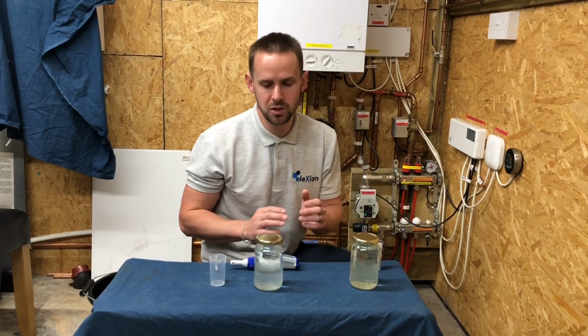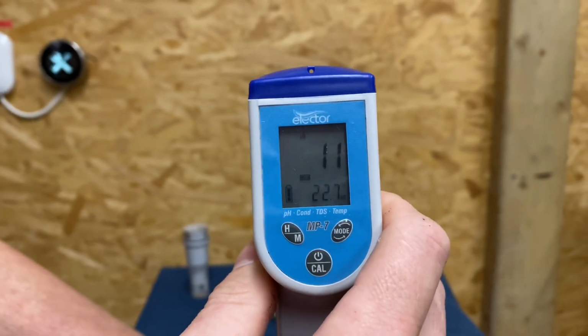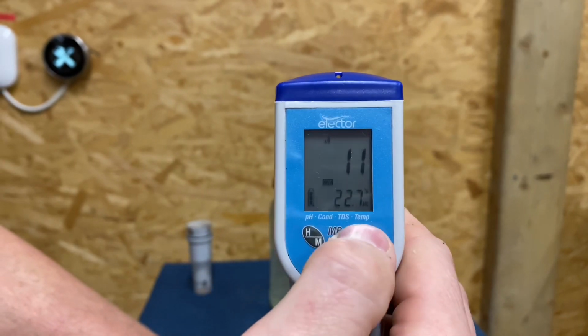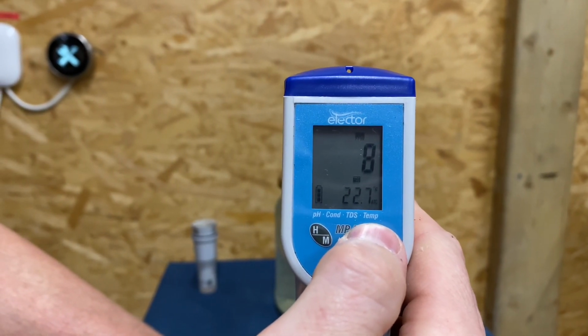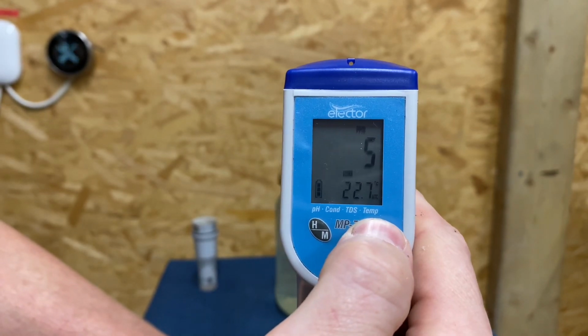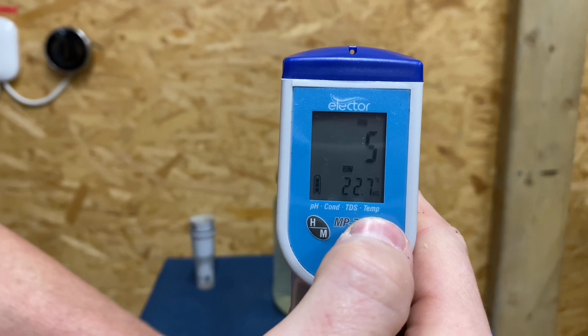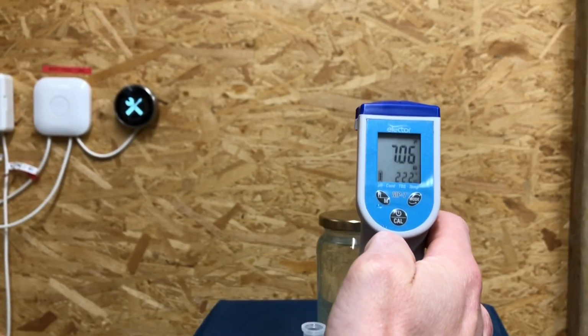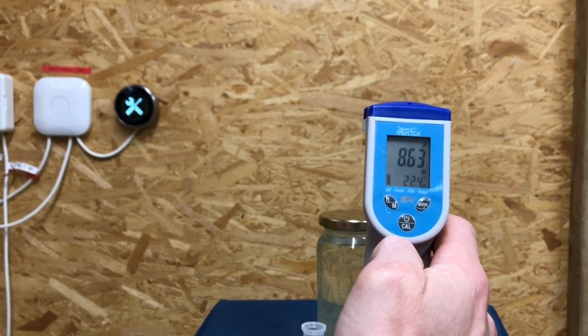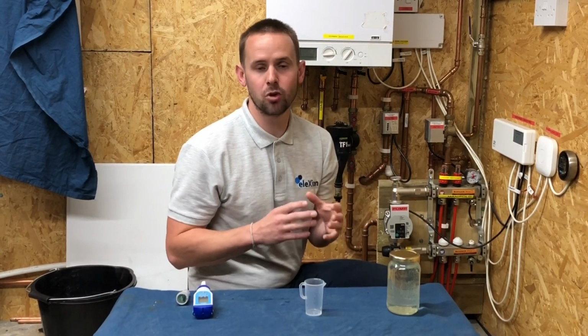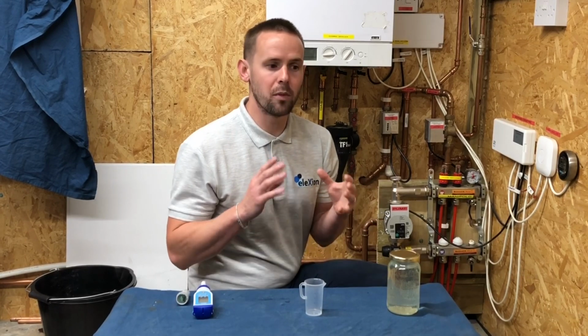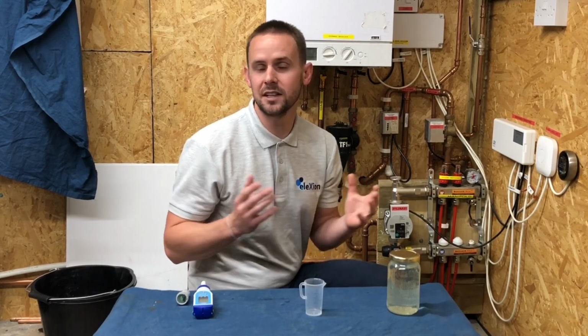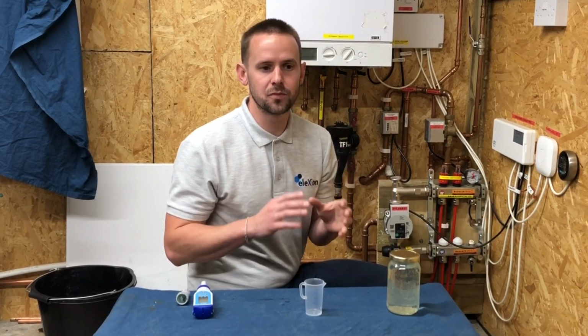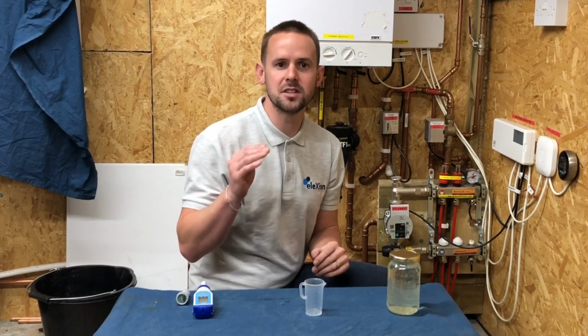Now I'm going to test the Clarimax water. Our conductivity here is 11 microsiemens. Our TDS has dropped to 7, 8. And our salts have dropped to 5 parts per million. So this is the water from the Clarimax. Change the probe over, we're just going to do the pH on the Clarimax. It's about 8.6. That little test shows that the water that comes out of the Clarimax is already ideal for our heating systems. So when we're filling with the Clarimax, we know we're going to leave the system as we intend it to be. When filling the system, you don't want it 100% demineralised, you want a little bit of conductivity in there, so above 10, but certainly less than 100.